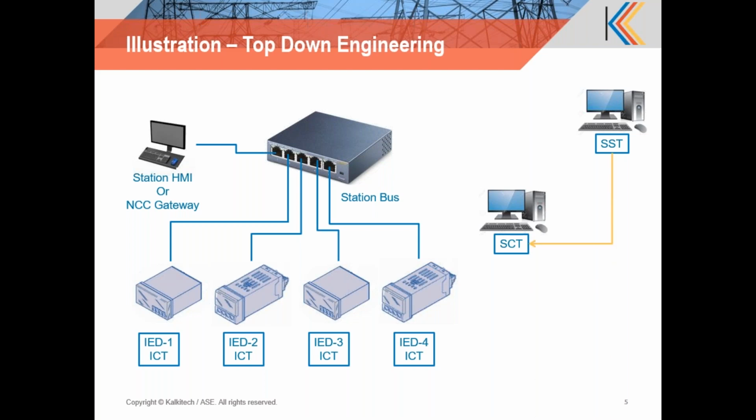The specification is generated as an SSD file, and this SSD file is imported by the SCT. So at this stage, the system configurator, the user of the SCT tool, has a clear picture of the requirements of the system, and he either generates or solicits IED ICD files. Let me just set up my pointer here.